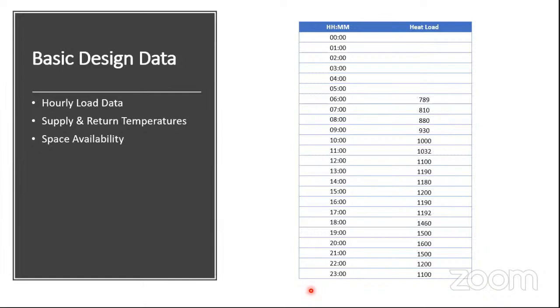So what is the basic data that is required for designing a thermal storage system? In the first place, we need hourly load data, and it should be like this: heat load, let's say this is the heat load. This is the hourly load. These are 24 hours, and this is generally the peak load, and very often the diversified load across the entire building or a campus. Then we also need supply and return temperatures, that is, what is going to be the supply and return temperature across the load. Space availability is also something that should be observed if planning for a chill water thermal storage tank.